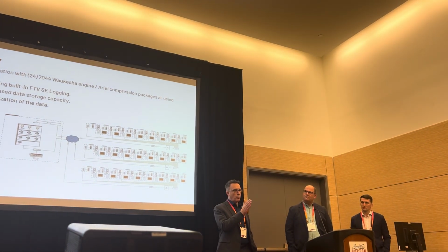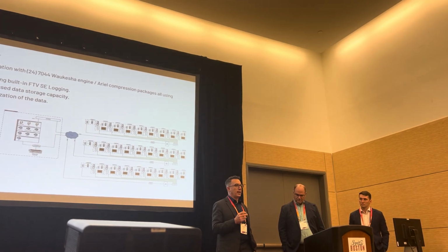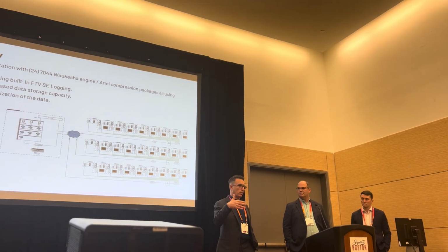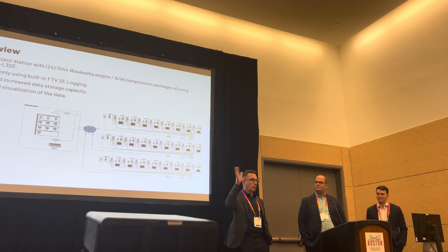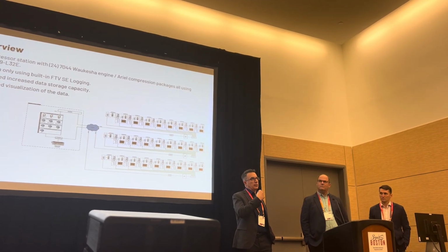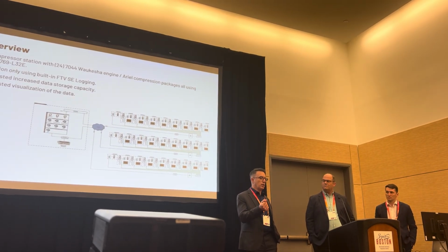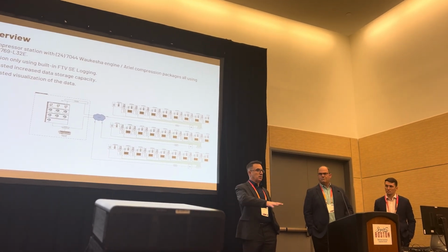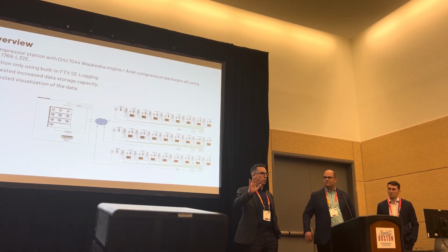But if you're polling at 15 minutes, you're not going to deploy somebody out to a remote area off one bad poll. I'm going to wait 45 minutes or an hour, if it's like Signet and it gives you magenta on there. I'm not going to say, oh, at this one, we're rolling. You're going to wait. Last January, I was at the EPA conference and I said, what's the sweet spot, guys? They said, if you were doing 60-second polling, and you could identify something in 5 minutes, the EPA and DOT would be totally happy, and that would be completely acceptable.